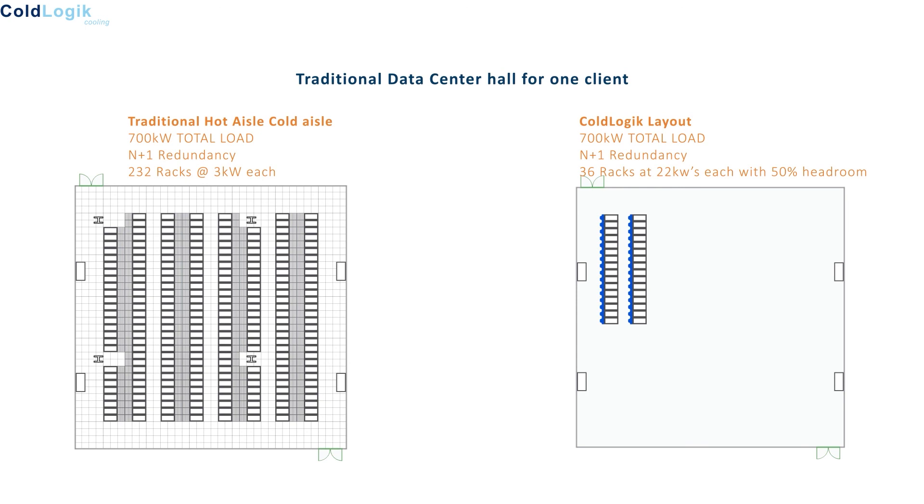Using the same water supply parameters as traditional data center cooling, each rack would now house 22 kW of IT load with the same N+1 redundancy. But instead of 91 kW power draw, the ColdLogik RDC only uses a total of 8.7 kW, which represents over 90% energy saving. Furthermore, each RDC would allow each rack to increase by another 50% additional load, taking it to 33 kW per rack, future-proofing the data center for higher-duty chipsets due to arrive within the next 5 years.